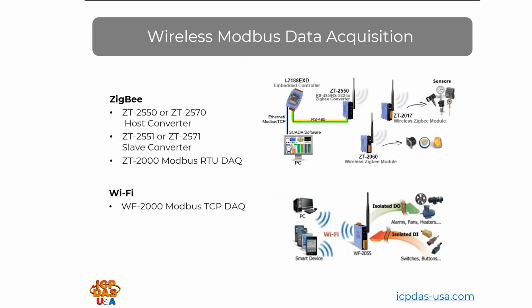In addition to the wired type of data acquisition equipment, there are also wireless options like our Zigbee ZT2000 series, which communicates over Modbus RTU. Zigbee is an intelligent self-organizing mesh network. It supports line of sight communication up to 700 meters or 2,296 feet. Each endpoint is a repeater, so whether it's an I/O module, or a host converter, or a slave converter, it acts as a repeater. If there's any obstruction in the communication path, the host coordinator, which would be connected to your controller or your computer, would reroute the communication around the obstruction, since each end device is a repeater.